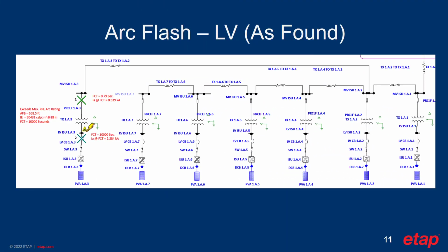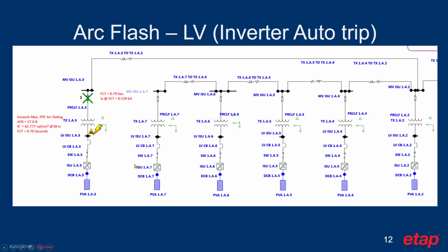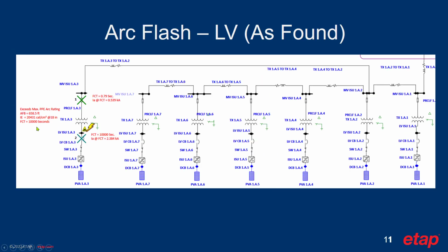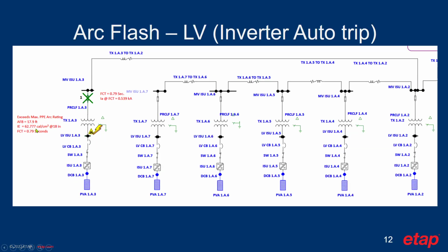Switching back to the presentation, I could say here, with the as-found settings without the auto trip feature enabled in ETAP, the incident energy was really high and unrealistic. And even the 2-second rule would still not give you the ballpark of 40 calories per centimeter square. So using the auto trip, we were able to make sure the fuse would clear the fault at this particular current level seen by the fuse from the arcing current point of view.